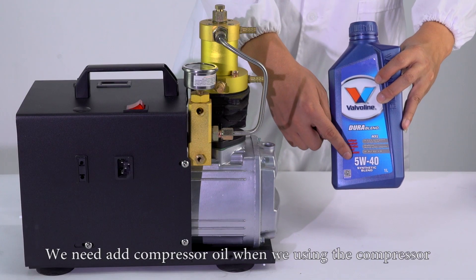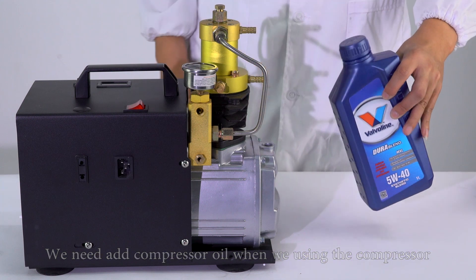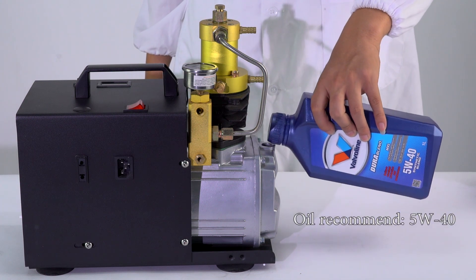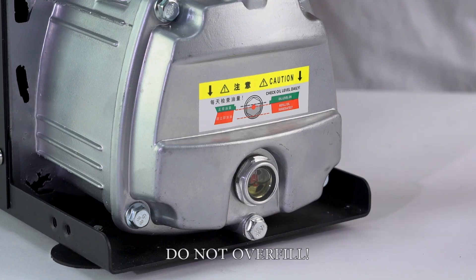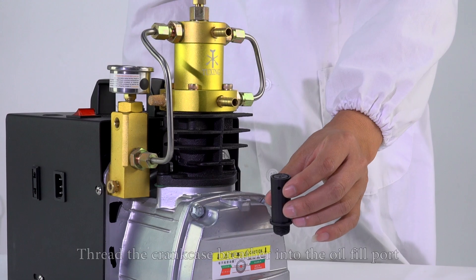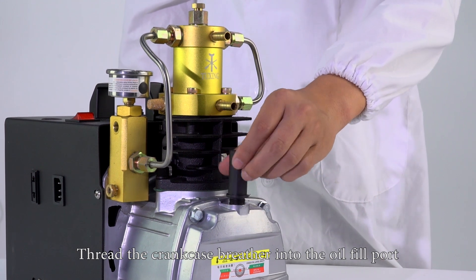We need to add compressor oil when we are using the compressor. Oil recommended is 5W-40. Fill oil up to the red indicator dot. Do not overfill. Thread the crankcase breather into the oil fill port.